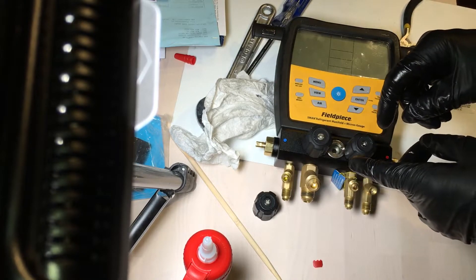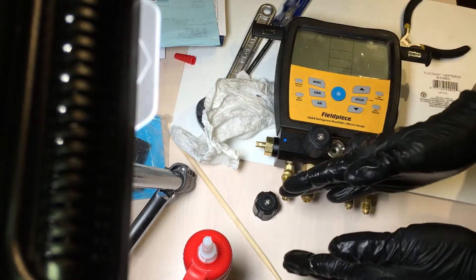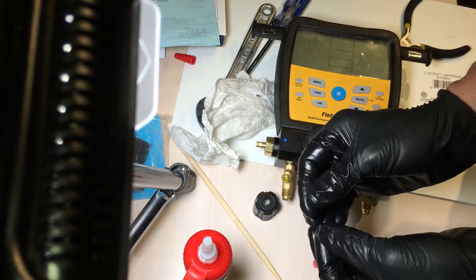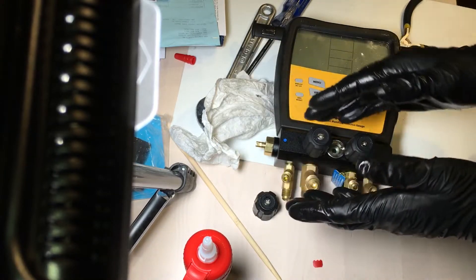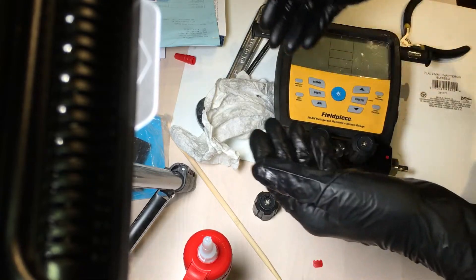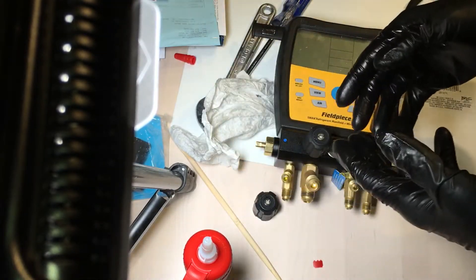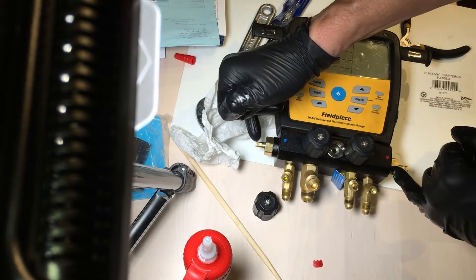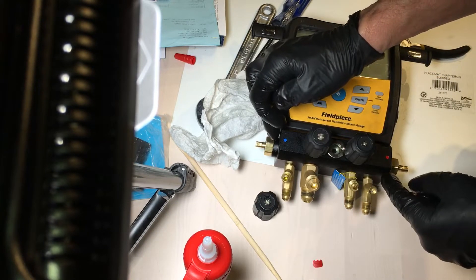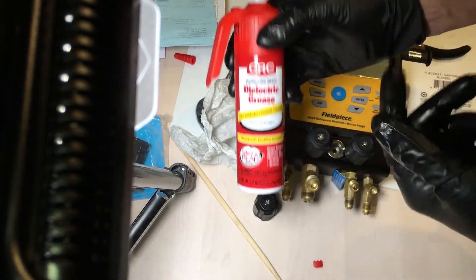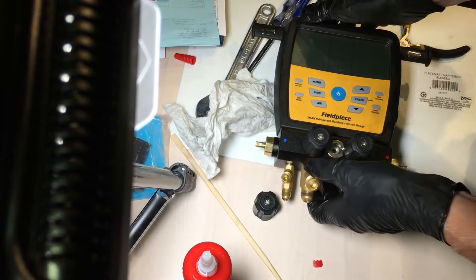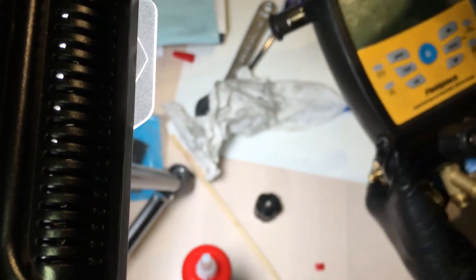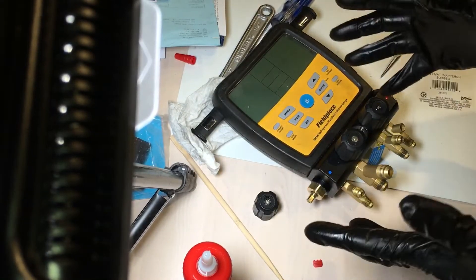But if you did want to try and you think you had some problems with leak from your manifold because you isolated your hoses, you put your micron gauge on them and found out when you're hooked up, for some reason it doesn't matter if it was a Testo, a Fieldpiece, a Yellow Jacket, a Brute, or whatever brand it was. If you feel that you have any leakage through the o-rings and the seals inside here, a little dielectric grease or Nylog will take care of that problem and you'll have that equation out of your possible leaks. Put it back together, real simple. All right, see you guys.